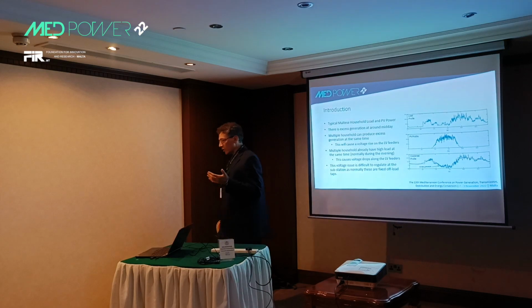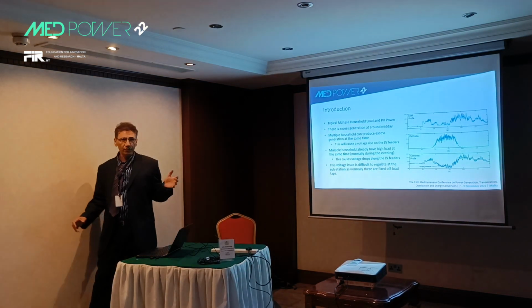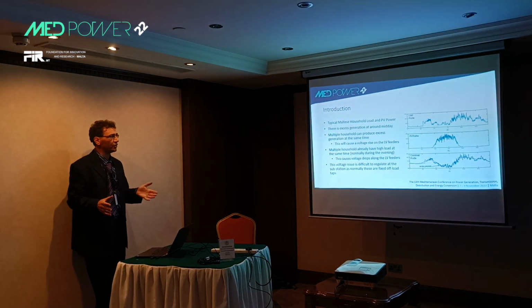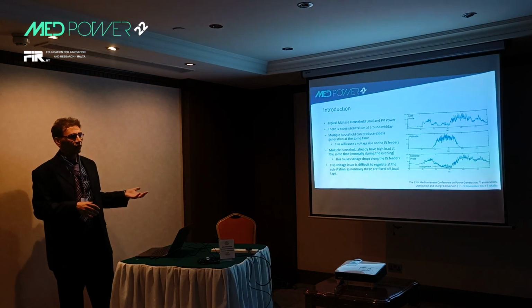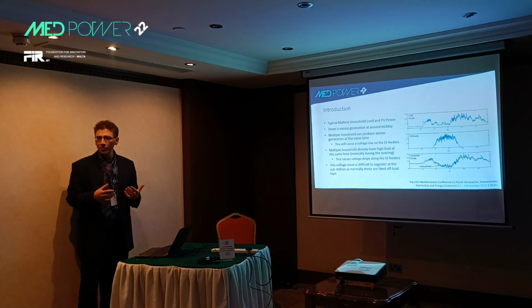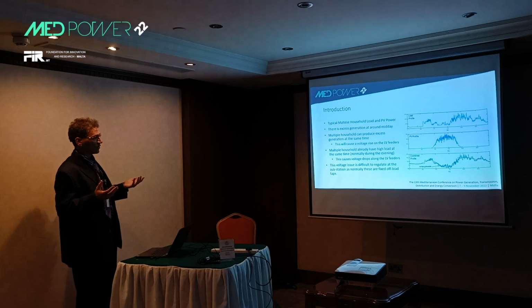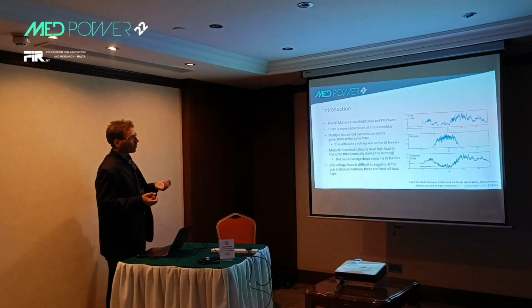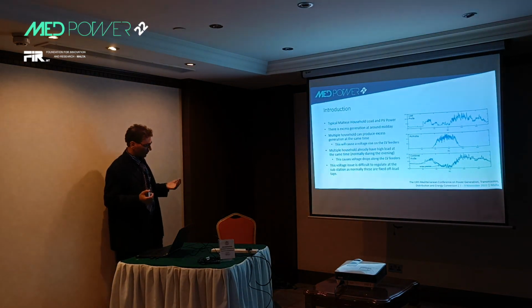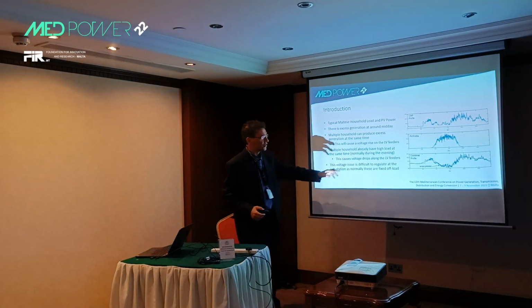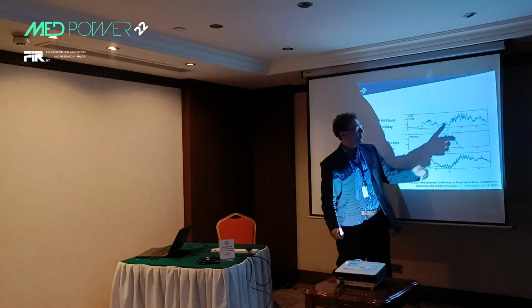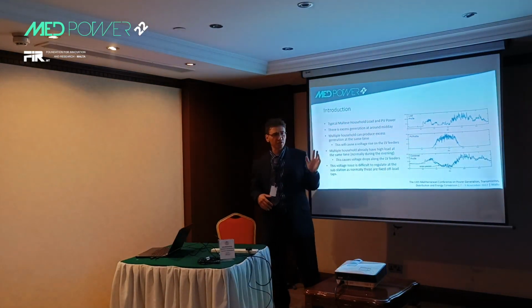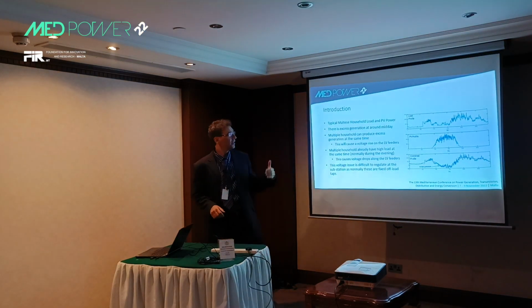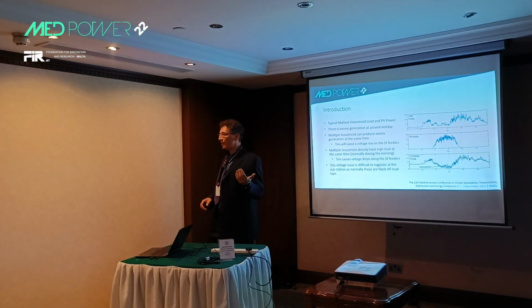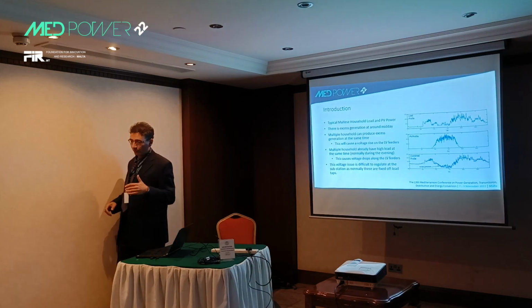Now in an island like Malta, if everybody is at work and the whole residential area start to generate power into the grid, the voltage along the transmission lines will go up. That is a problem. Also, on the other hand, when people return from work at night, you can see the loads go up. Everybody starts to cook, turn on their computers, televisions, Nintendos, etc. The load goes up, and on the other hand, the voltage goes down.